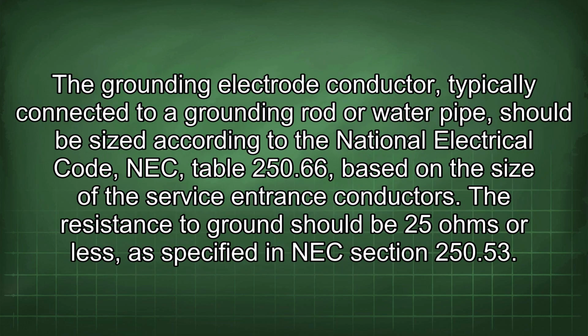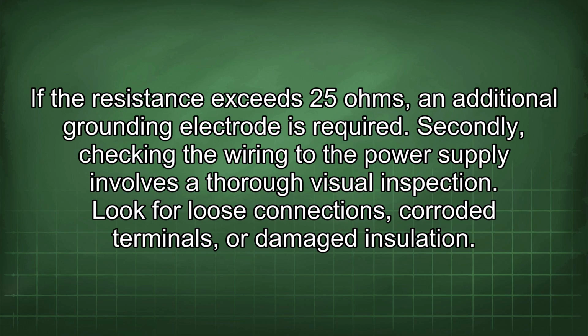The grounding electrode conductor, typically connected to a grounding rod or water pipe, should be sized according to the National Electrical Code, NEC, Table 250.66, based on the size of the service entrance conductors. The resistance to ground should be 25 ohms or less, as specified in NEC section 250.53. If the resistance exceeds 25 ohms, an additional grounding electrode is required.